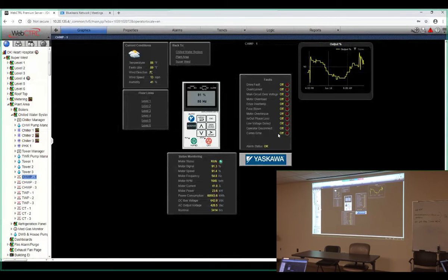The box below the drive itself gives you the status that the drive's currently running in. This one's running 91.3%. So the signal's what I'm sending it, the speed's what I'm reading back. The speed and the frequency are what I'm reading back from the motor, or from the drive. RPM, current, power consumption, bus voltage, and the AC output voltage.